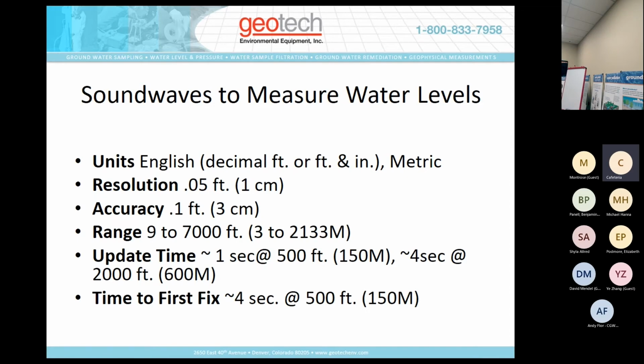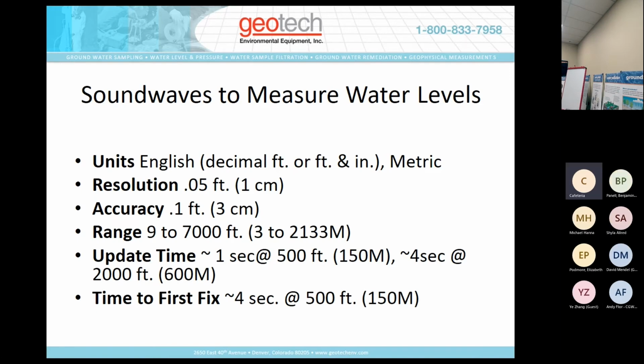The sound waves are resolution of 0.05, so 5/100ths of a foot. The steel is 1/100th of a foot. So making a decision on what's the best tool for the job, that degree of accuracy is going to be pretty important. The range is from 9 feet to 7,000. I mentioned our water level meter limitation for a tape is 3,000 feet. I think that's pretty standard industry-wide. So if you have something that's greater than 3,000 feet, and there aren't a lot of places that that's an issue, but some places in Nevada, I know that the water table doesn't start until about 2,500 feet. It's a big, deep hole in the ground before you find water.